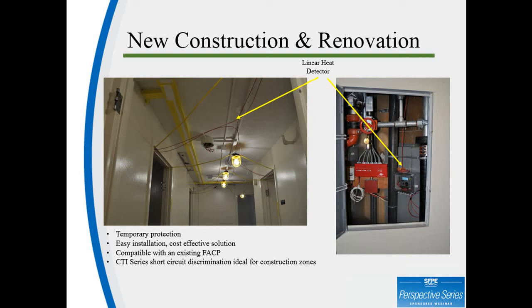The reason the CTI series is popular for this particular application is because of its short circuit discrimination. Damage to this detector does not cause an alarm condition. There's not a lot of information about temporary detection in NFPA 241, but most of the AHJs we've encountered so far have been very receptive to this approach.